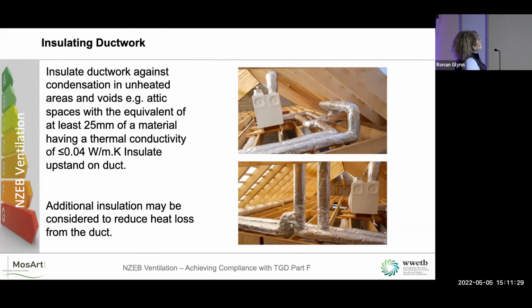Again, insulating ductwork. So if you're insulating ductwork against condensation in unheated spaces, you must have the equivalent of 25 mil of a vapor type material having a thermal conductivity of less than or equal to 0.04 watts per meter Kelvin. So they're really getting down in the weeds about what type of insulation. And again, you must insulate the upstand on the duct. So 9 times out of 10, it'll stop there at the ceiling level. And then they don't insulate the upstand. So we normally have about 150 mil upstand if we don't have a roof vent or a tile vent. So what happens is in the last 150 mil, it will just condense and run back down into the unit.